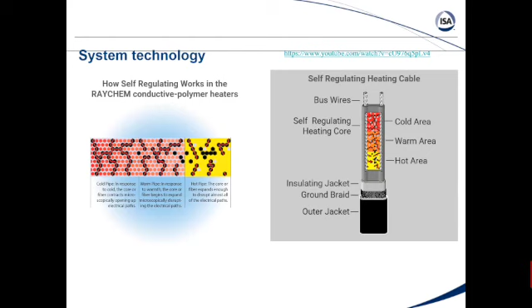Now I'll say self-regulating, and that's what it's called, and that is what it's doing. But keep in mind that it never shuts off. It will reduce its output and it will increase its output based on the temperature, but it will never completely shut off, which is why there is a definite need for control of this cable. And I'll talk a little bit about that before I start talking about the MI cable. The most blaring example and the most common issue with self-regulating cable, we see a lot with safety showers.